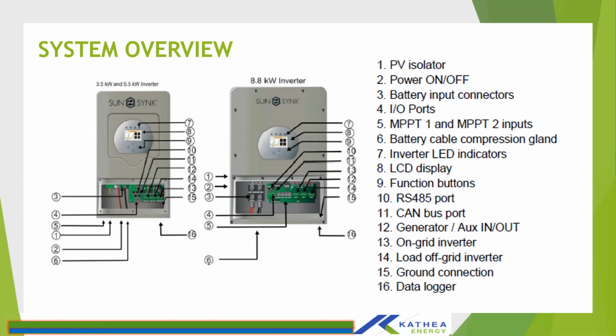Mostly if you are using lithium, most lithium batteries use a CAN bus, so you terminate on item 11 on the diagram. Then it offers 3 termination ports. All these ports can work as output. 2 of them can work as input. So we have the grid port, which is a grid input to the inverter, and at the same time, the inverter uses this port as an output port to backfeed power to the non-essential sides.